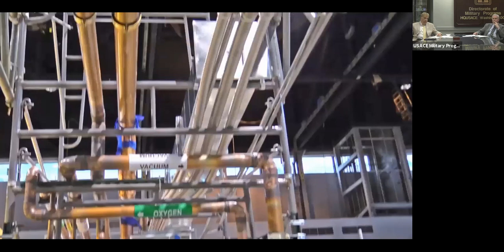After they're done and everything is brazed, we test it with air to make sure there are no leaks. We do that with 100 to 150 PSI—we'll hold 150 PSI here for 24 to 48 hours to make sure there are no leaks.